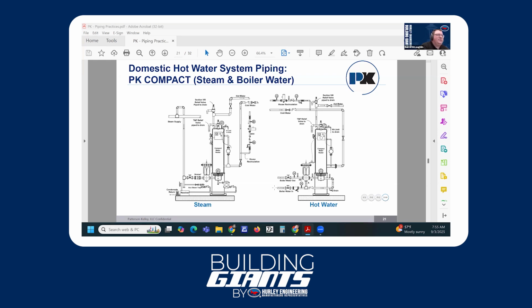There's a lot of things that go into the design of systems with brazed plate and plate and frame heat exchangers for potable systems. So at times the shell and tube can be a little bit of an easy button. They're a little bit easier to plug and play with. But we see them more often in the low temperature or the low delta T applications, right? So we'll typically operate these at 20 to 40-degree deltas, and we might operate the brazed plate at like 60-degree deltas, depending on what our system calls for.